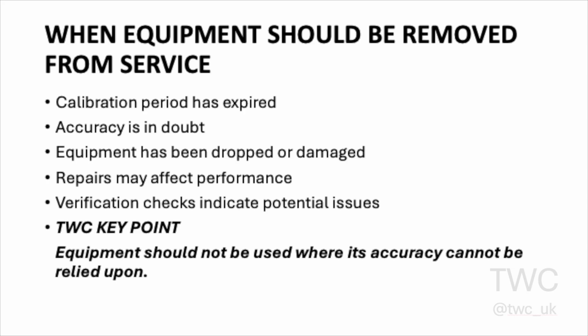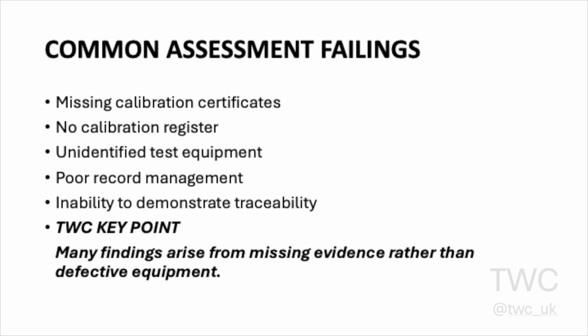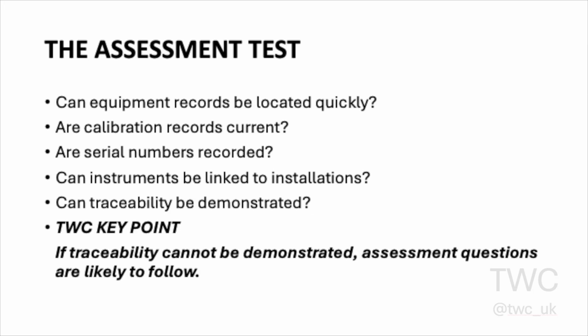Many calibration-related findings are not caused by faulty instruments. More commonly, assessors encounter missing calibration certificates, incomplete records, unidentified equipment, or an inability to demonstrate traceability. The evidence may exist somewhere within the organisation, but if it cannot be produced efficiently during assessment, it may still become a concern.